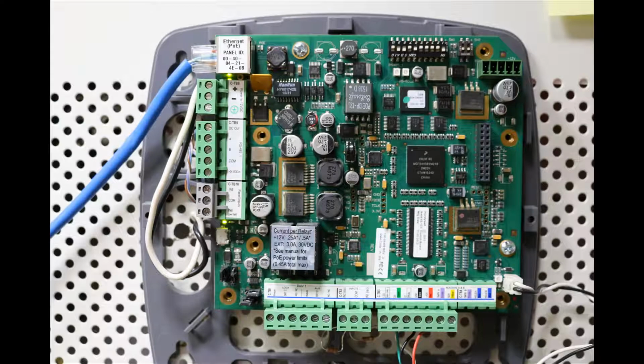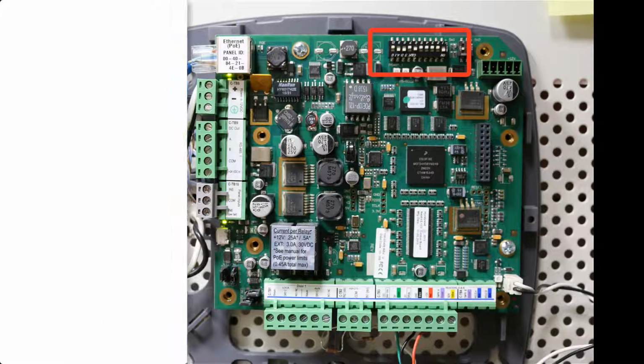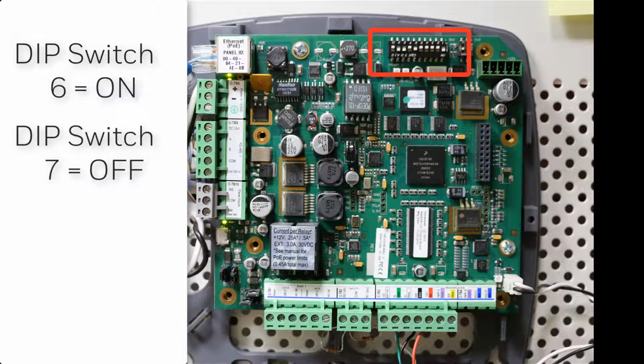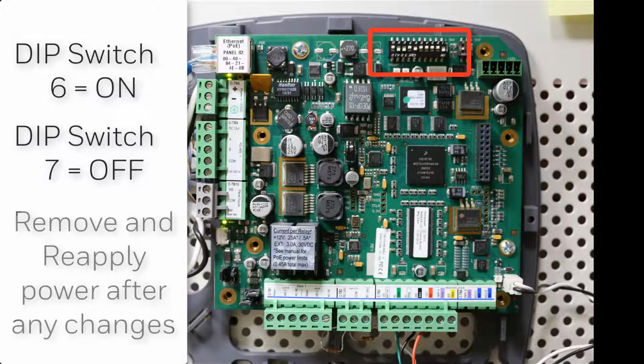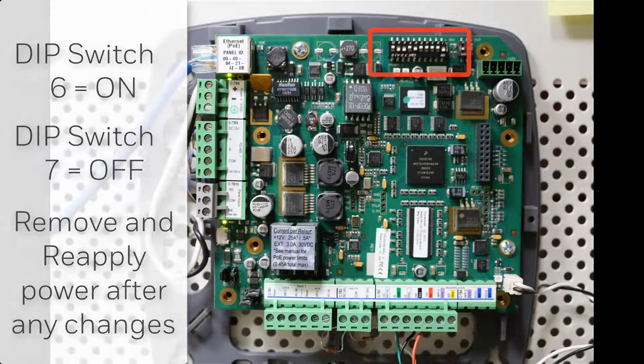If the MAC is correct, verify the DIP switch settings on the panel. The panel must be set as a gateway panel, so ensure that switch 6 is on. Usually the panel will not be using the default IP address, so also check switch 7 to see if it is off. If 7 is on, this can affect the panel's ability to communicate on the network. If the DIP switches need to be changed, be sure to power cycle the panel after changing them and check the registration status in MAXPRO Cloud.